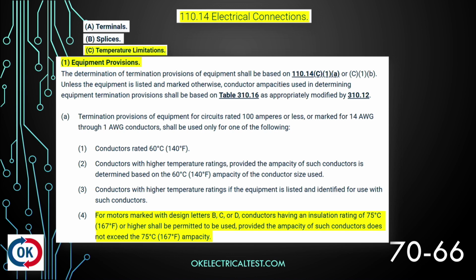All right, so let's get back to this 110.14 electrical connections, because there is something that we need to highlight here. Under letter C, temperature limitations, we've got number 1, equipment provisions. So these are equipment provisions for temperature limitations for electrical connections. We're going to jump down to number 4 down below there, and it says for motors marked with design letters B, C, or D, conductors having an insulation rating of 75 degrees or higher shall be permitted to be used. So I can use a 75 or a 90 degree conductor, okay? But let's read on. Provided that the ampacity of such conductors does not exceed the 75 degree ampacity.